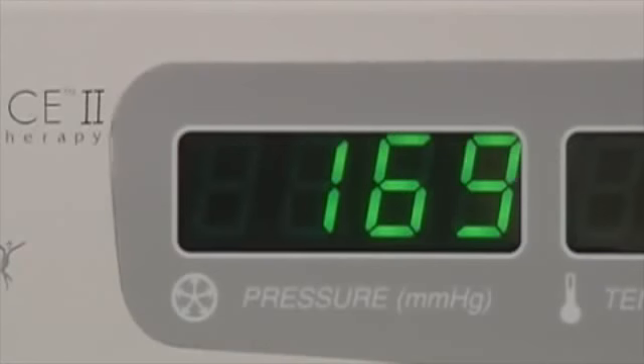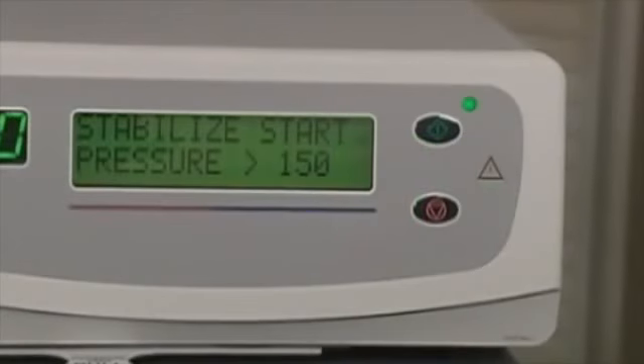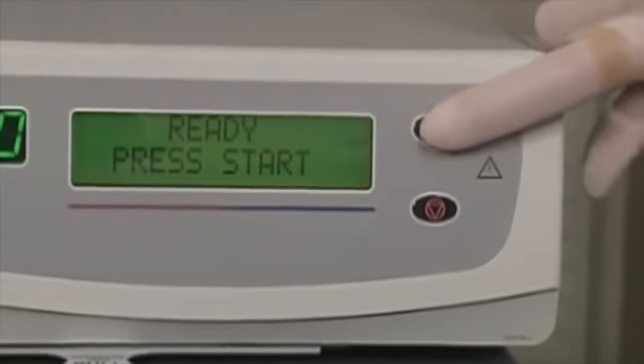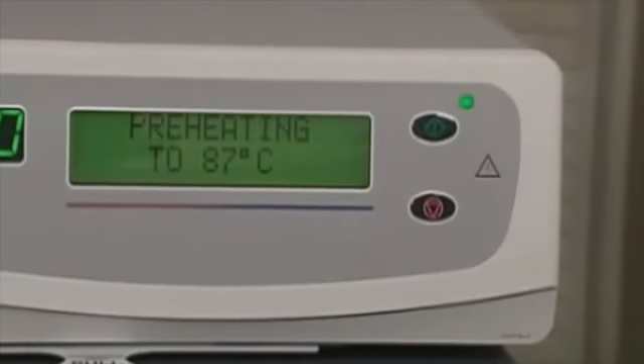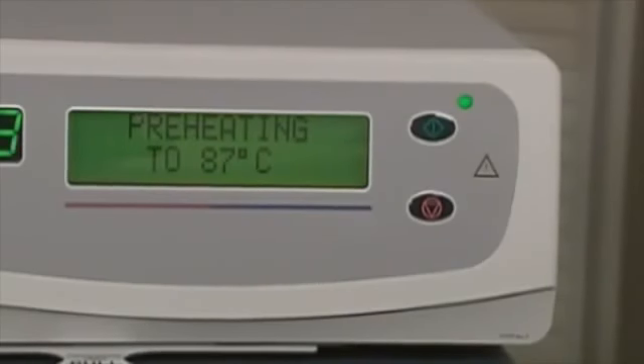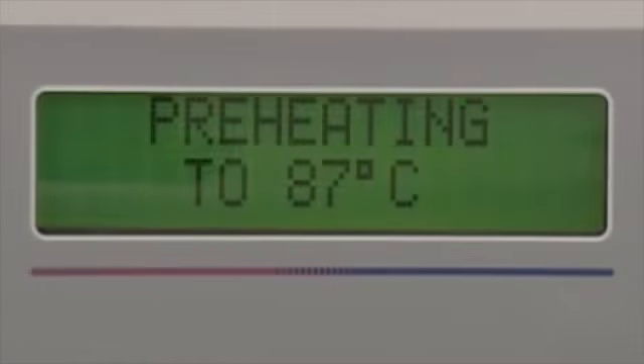Once a steady pressure of 160 to 180 millimeters mercury is maintained, the message display panel will read, "Ready, press start." Press the start button on the controller. Once started, the controller activates the heater to achieve a treatment temperature of 87 degrees centigrade or approximately 188 degrees Fahrenheit. This normally takes between 15 to 45 seconds, but can take up to 4 minutes.